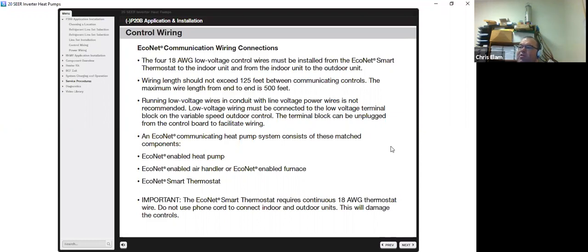An EcoNet communicating heat pump system consists of these 3 components. EcoNet heat pump or AC, EcoNet air handler or EcoNet enabled furnace, and an EcoNet thermostat. It is important to note that EcoNet smart thermostat requires continuous 18-gauge thermostat wire. Do not use phone cord to connect with indoor outdoor units. This will damage the controls. You will also have poor communication.